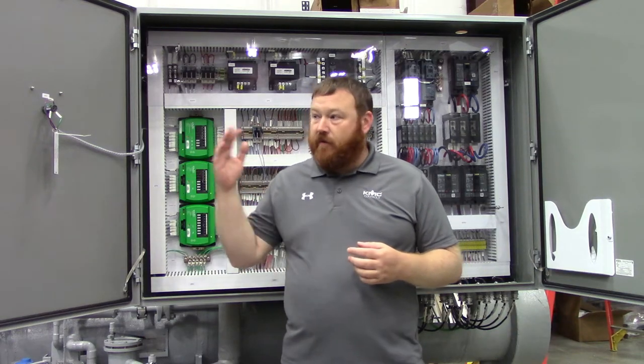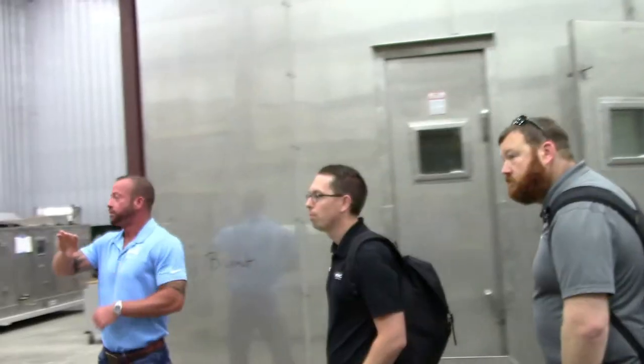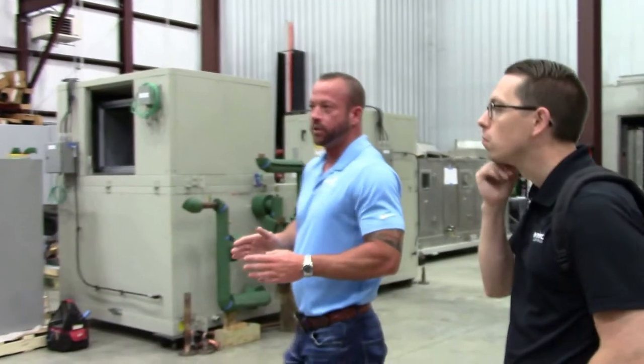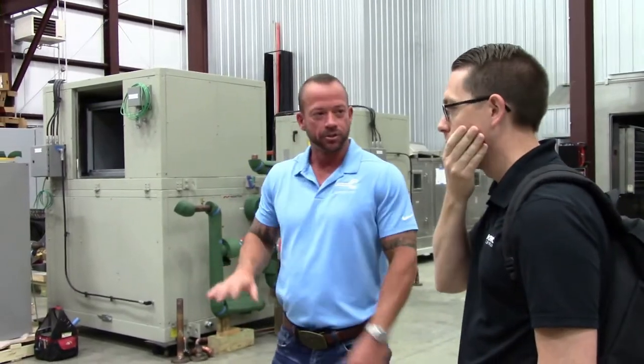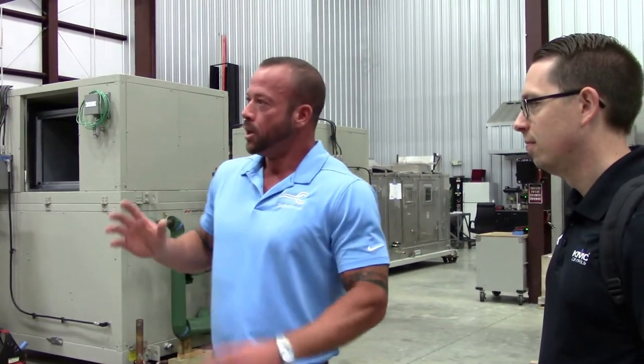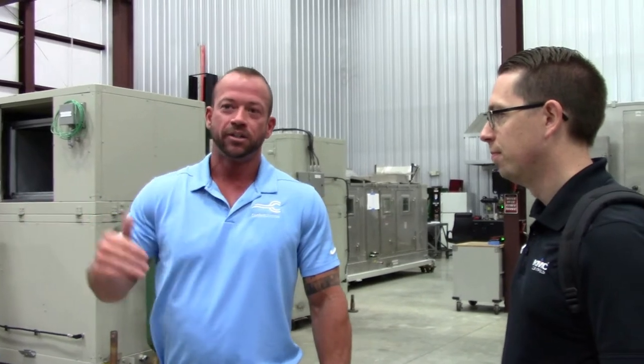All the sensors, all of the actuators on the air handlers. This job is a chill-off — an existing rig that's in the Gulf, actually in production right now. So we have to replace all five air handlers and all three chillers without bringing any lag down. We're going to bring a temporary unit out there as we change out the air handlers.